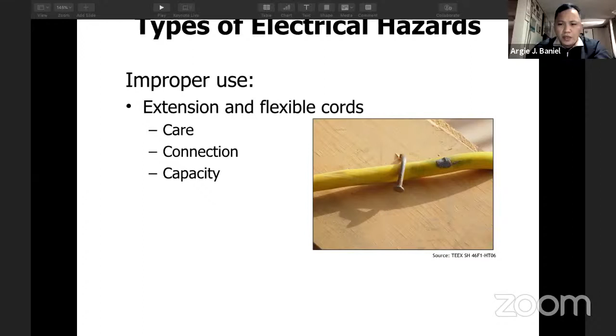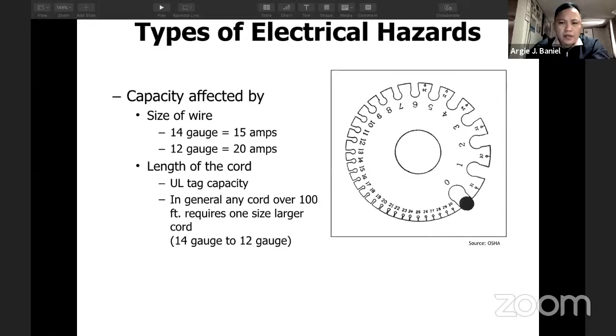Improper use by using extension flexible cords. So walang care, the connection and then the capacity. Capacity affected by the size of wires. 14 gauge which is a 15 amps, 12 gauge which is a 20 amps, and then the length of cords, UL tag capacity. In general, any cord over 100 feet, it requires one size larger cord. Diba? Gumagamit ka ng gauge 14, so if it is 100 feet, so magagamit tayo ng number 12, which is one size higher or larger.